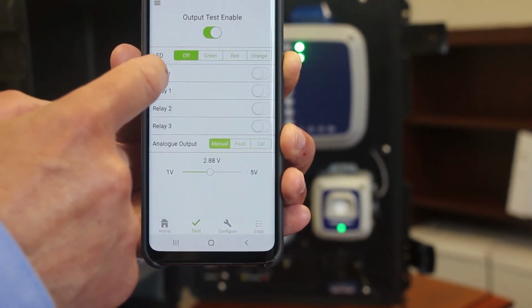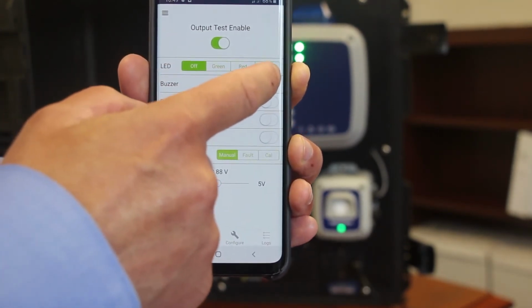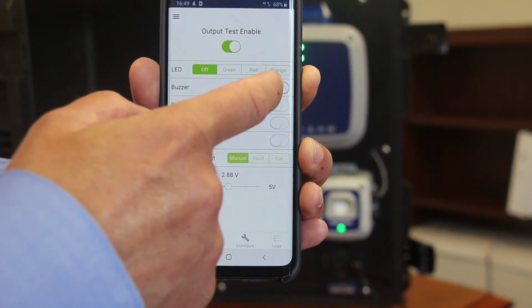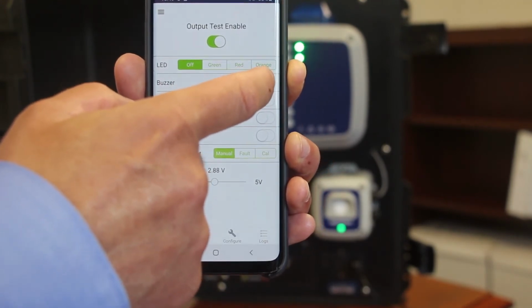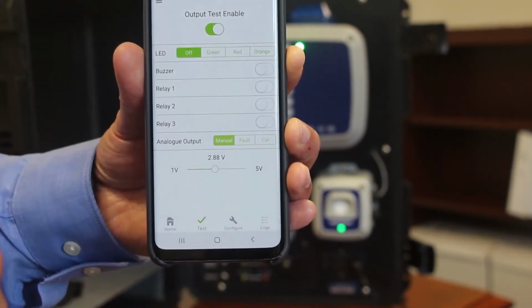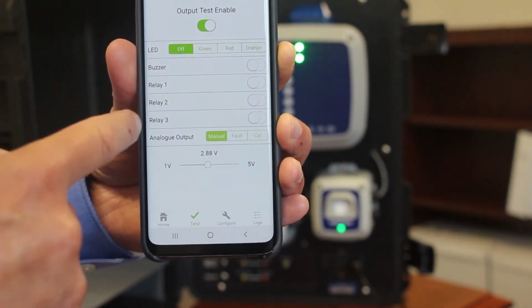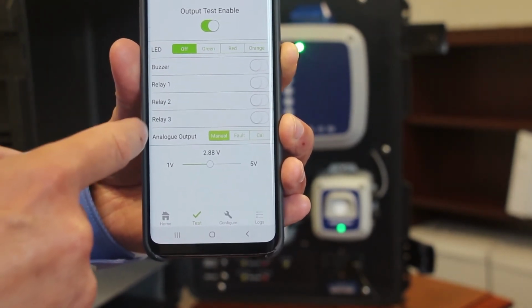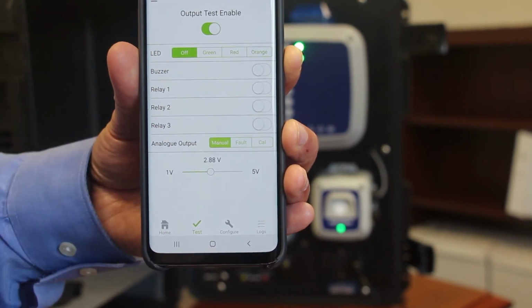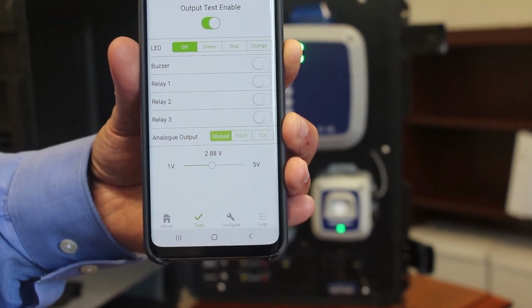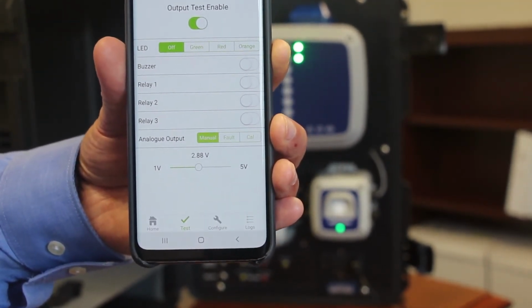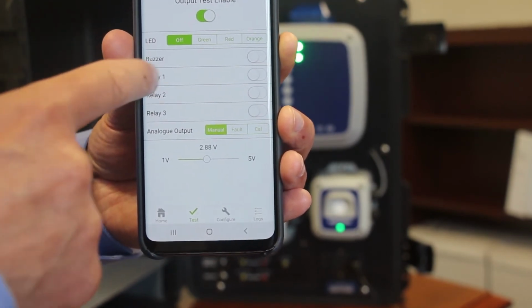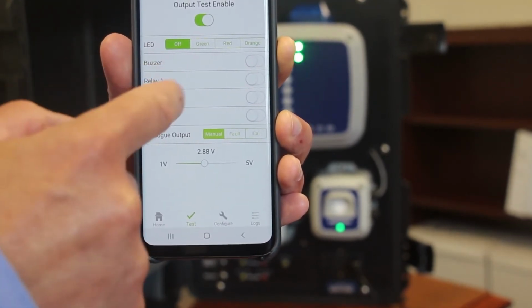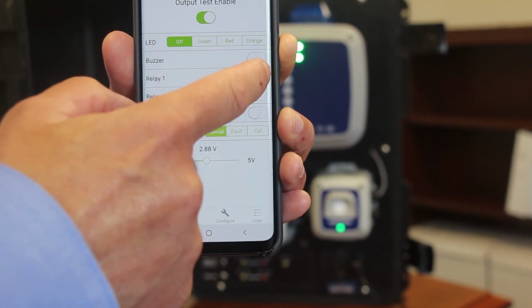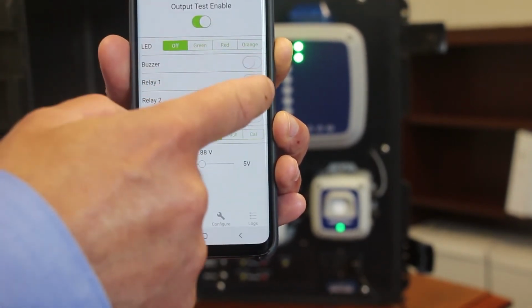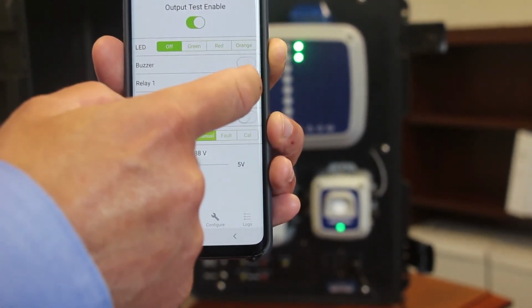You can test the internal buzzer to make sure that it operates correctly. You can activate the different relays on here. In a second, we'll show you on the MGS demo kit what that looks like in terms of the display. But just to highlight this, you have relay 1, 2, and 3. If I click on these, you'll probably hear the click in the background of the relay switching.